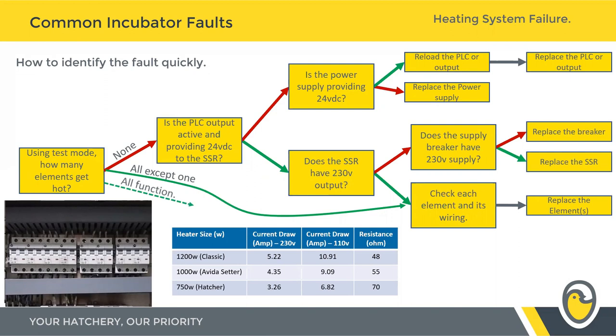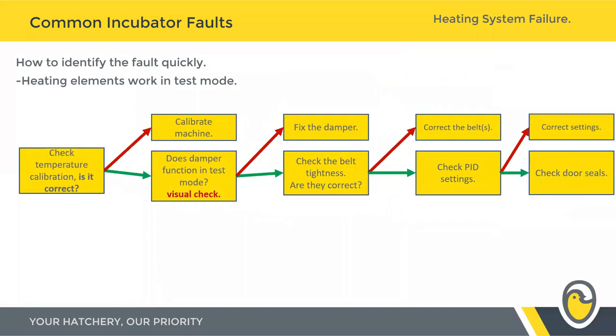If all your heating elements function as expected in test mode but you're still aware of a fault on the heating system, we move to a second diagnostic tree. This is the order we get our engineers to check the heating control systems — from left to right, most common to least common faults. Straight away, check the calibration of the machine — run through for a good hour or so to verify that the temperature probes are reading accurately. If one zone is calibrated too low, the control is going to artificially heat that zone, fighting the neighboring zones. All zones need to be tightly calibrated together.